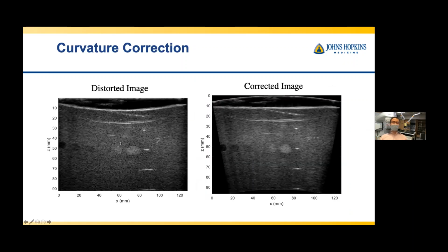On the left side is the distorted image without any information about the transducer element locations, and on the right side, after incorporating the transducer shape from the infrared camera, you are able to correct the image. You can see the contrast is much better. The problem is, in real clinical use, your infrared marker can easily be blocked by, for example, other imaging devices in the room. And as we know from ultrasound, if you are off by half of the wavelength, it may introduce other artifacts to your image quality.